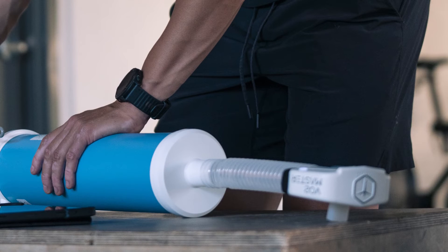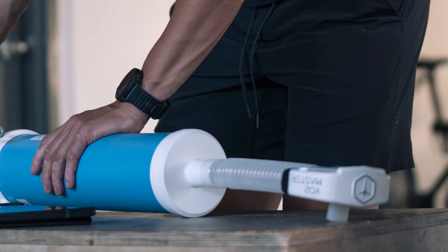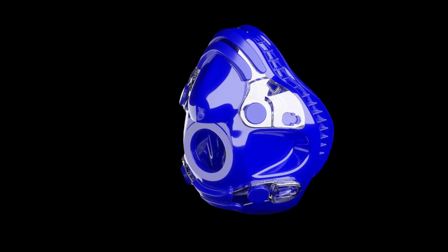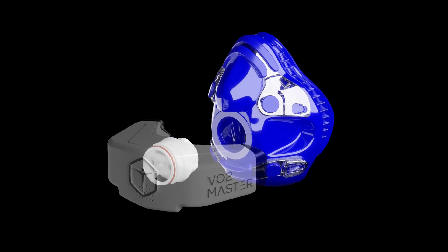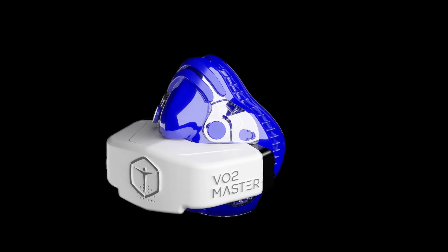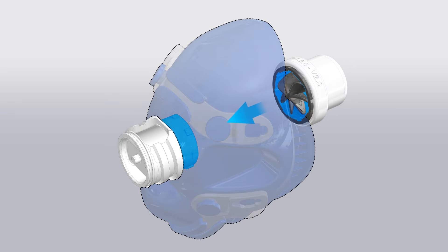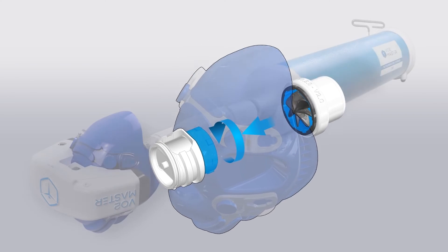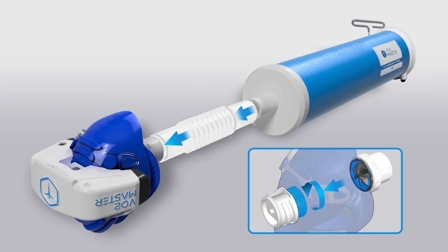If you have chosen to use the silicone adapter during calibration, ensure that the analyzer is positioned with the breathing port facing up and the tab of the adapter is facing down. This keeps the analyzer aligned and elevated above the working surface during calibration. For our example, we will be using the blue mask. We will push the user piece through the opening of the blue mask until the mask is resting on the user piece's shoulder. Next, we will thread on the calibration syringe adapter, then connect the calibration syringe flexible tubing to the syringe adapter and to the syringe. Note that the analyzer is to be positioned with the breathing port facing up during calibration.